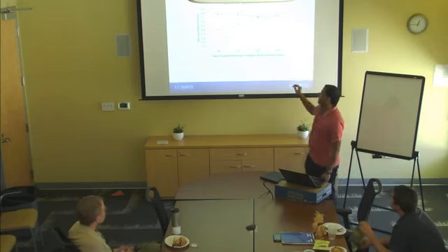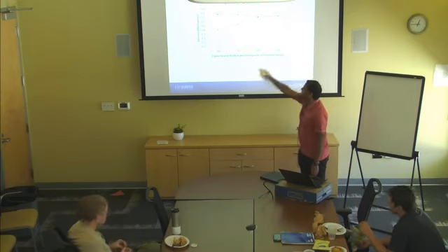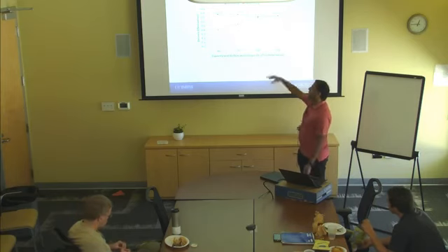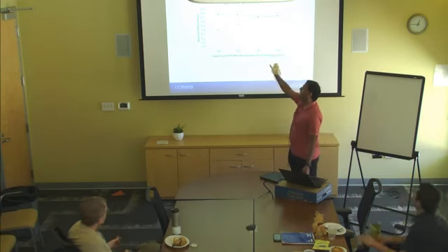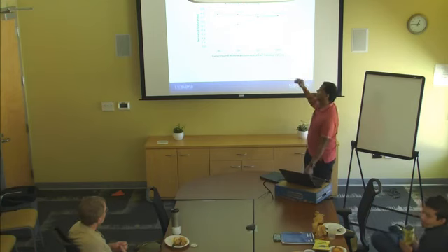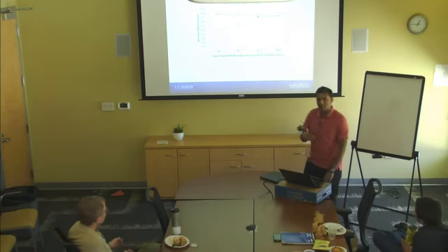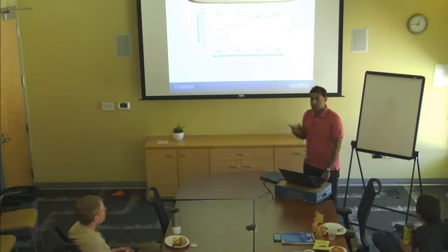What you are seeing here is that the delivery effectiveness decreases when all the ducts are carrying some capacity. But when only some zones carry capacity, in proportion, the delivery effectiveness actually goes up because the airflow rate and residence time don't change that much. The only losses that remain fixed are the return duct conduction losses.